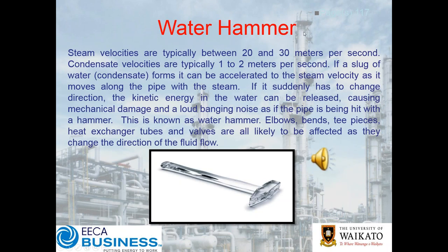So what is water hammer? We're going to talk with specific reference to steam and condensate systems today. In a steam system, steam velocities will typically be between 20 and 30 metres a second, or between about 70 and 100 kilometres an hour. Condensate velocities in comparison — the liquid phase in our two-phase steam condensate mixture — will typically be in the order of one to two metres a second. So greater than an order of magnitude slower.